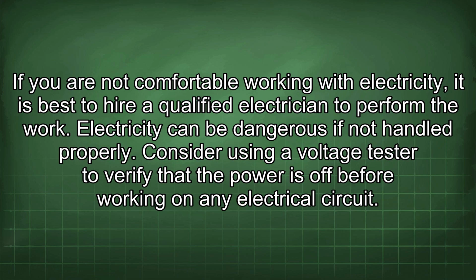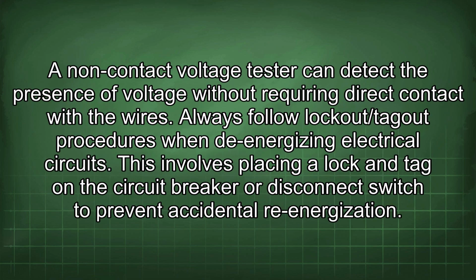Consider using a voltage tester to verify that the power is off before working on any electrical circuit. A non-contact voltage tester can detect the presence of voltage without requiring direct contact with the wires. Always follow lockout/tagout procedures when de-energizing electrical circuits. This involves placing a lock and tag on the circuit breaker or disconnect switch to prevent accidental re-energization.